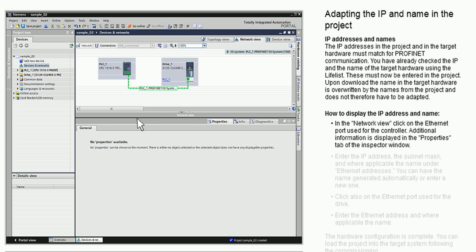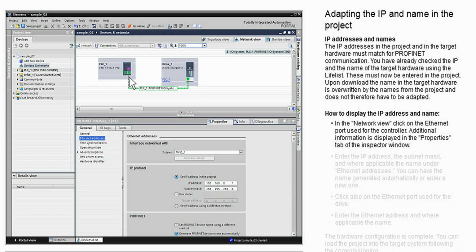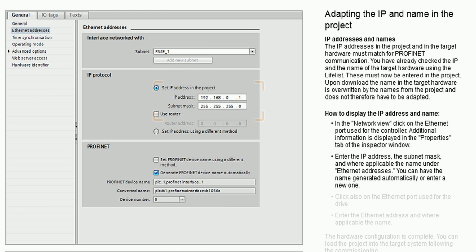How to display the IP address and name. In the Network view, click on the Ethernet port used for the controller. Additional information is displayed in the Properties tab of the Inspector window. Enter the IP address, the subnet mask and, where applicable, the name under Ethernet addresses. You can have the name generated automatically or enter a new one.